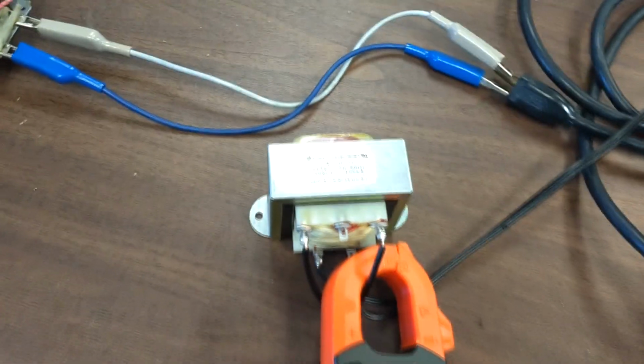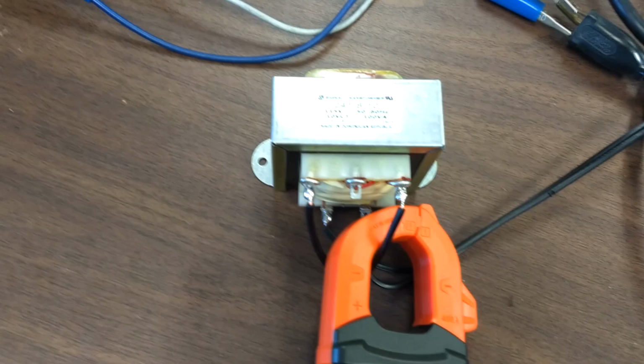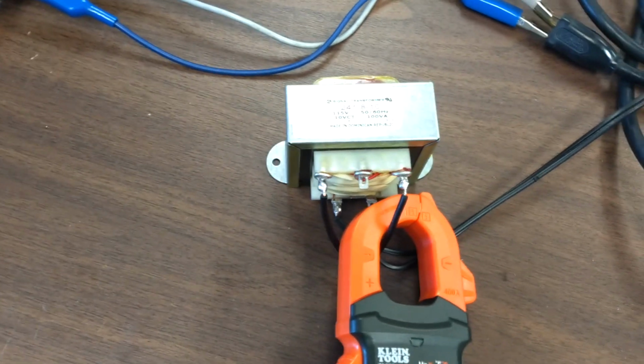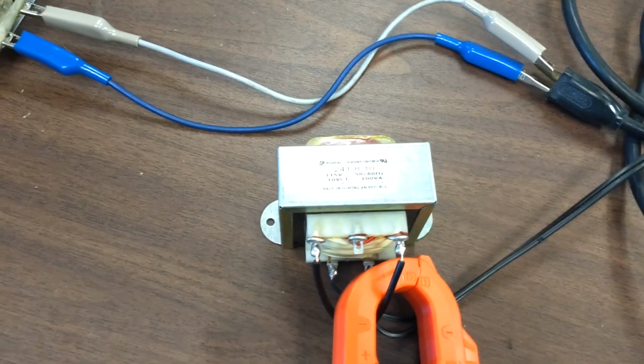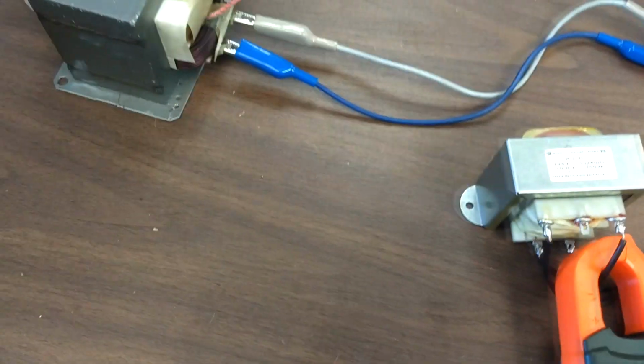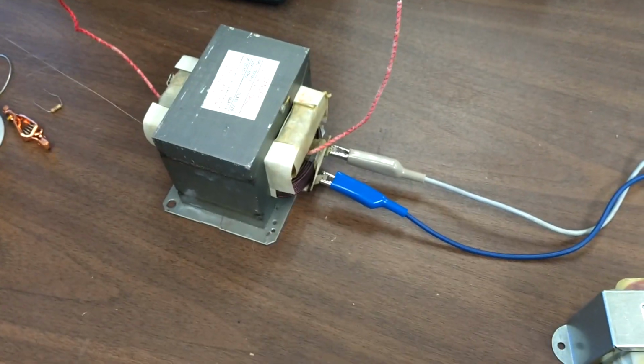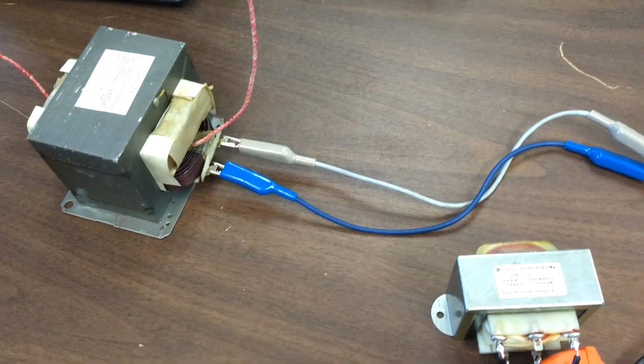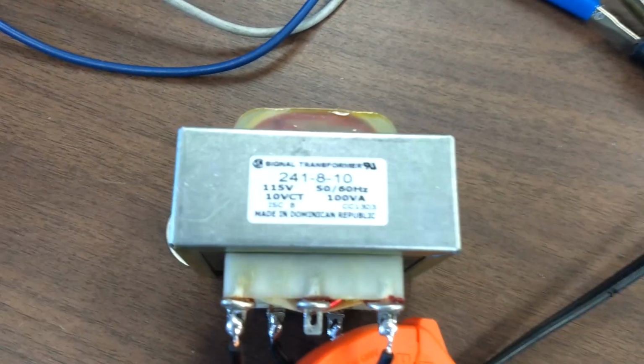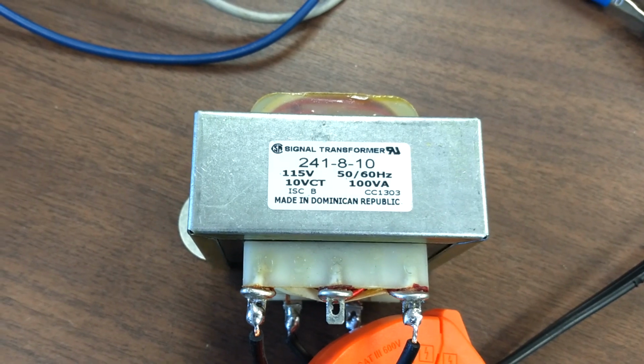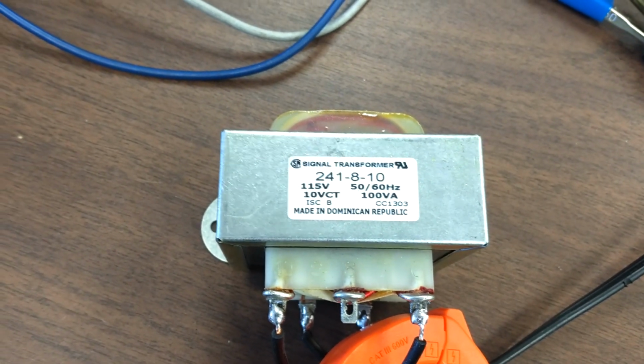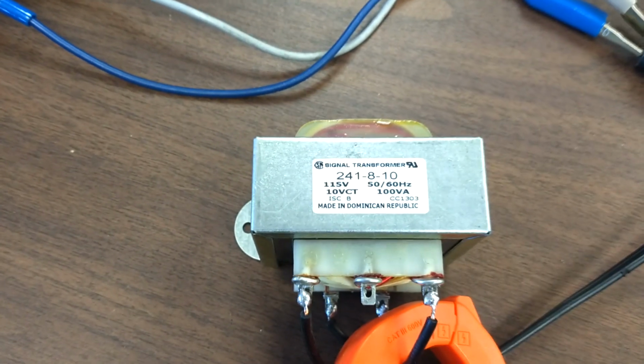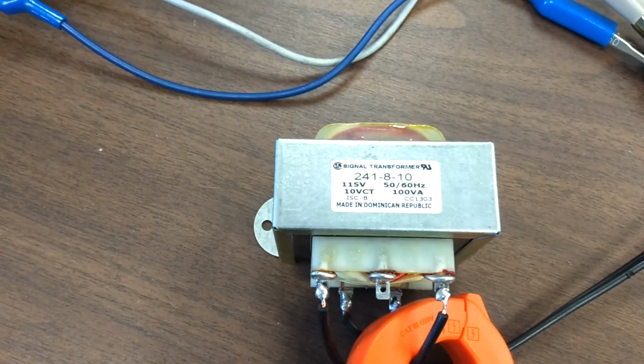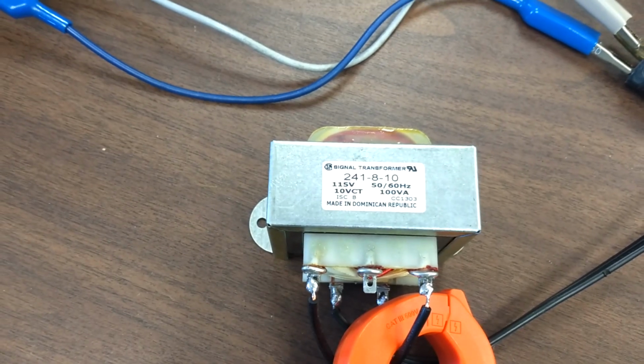We're drawing inductive current, which is 90 degrees out of phase with the voltage. Therefore, there's current draw, but there's no dissipation other than normal core losses, which are typically pretty low. So this demonstrates why transformers are rated in VA rather than watts, because you can draw inductive or capacitive current just like you can draw resistive current.